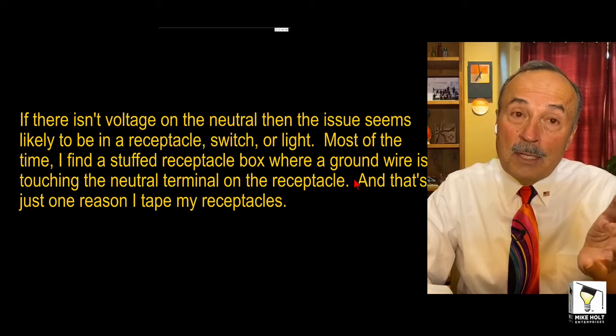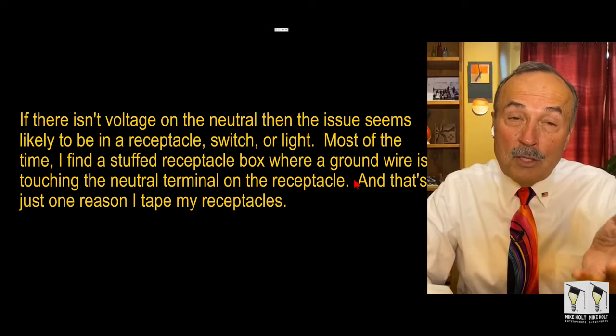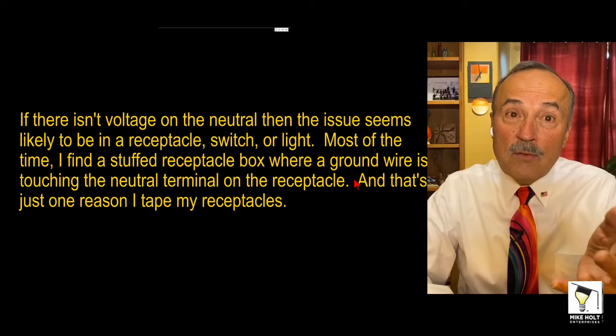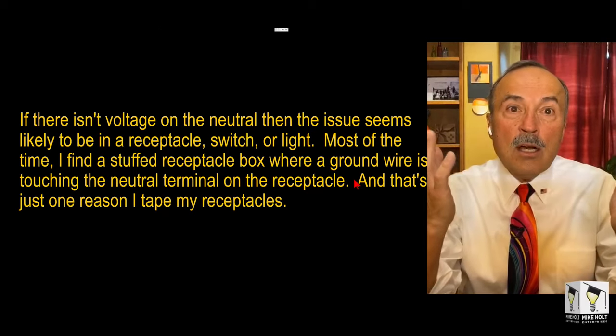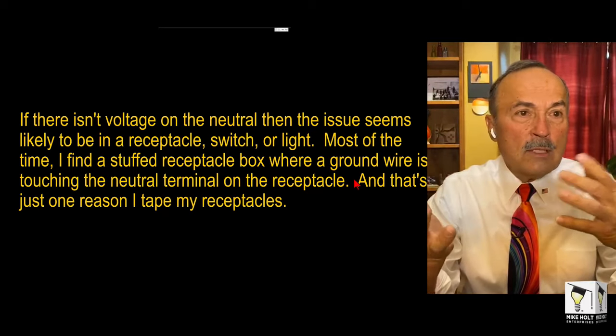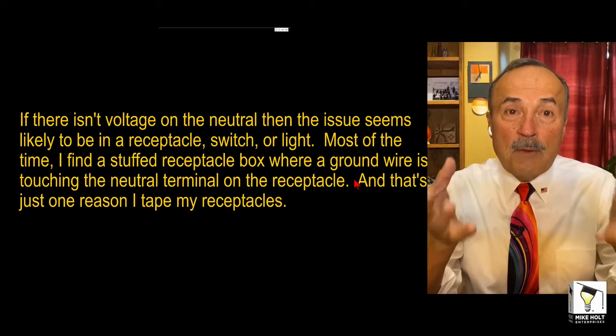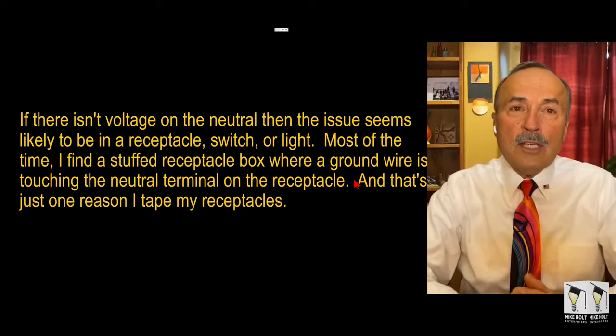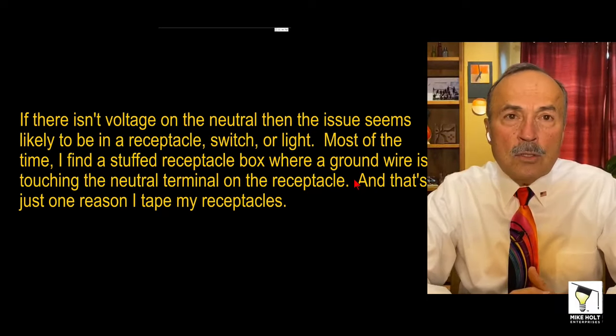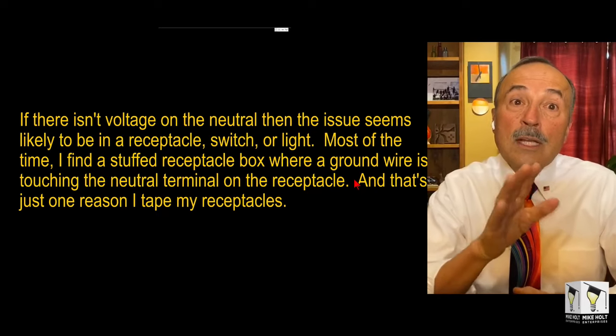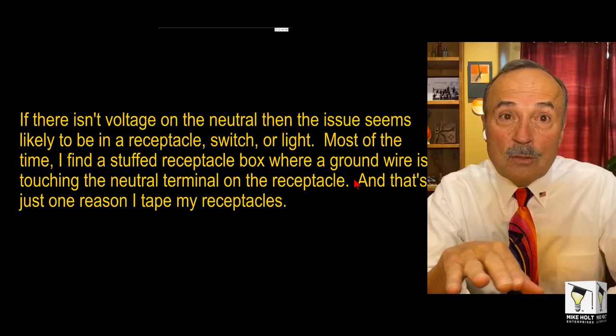But you've got to realize something. You've got to have the loads on to be able to detect whether or not there's any kind of sharing of loads. So you make sure you turn all the lights on, turn everything on, all the lighting and receptacle circuits, plug something in everywhere, keep everything going. Then you turn on the AFCI, it trips, you put an ammeter on that neutral, and there's no current on the neutral. You know what that means? It's not a shared neutral.